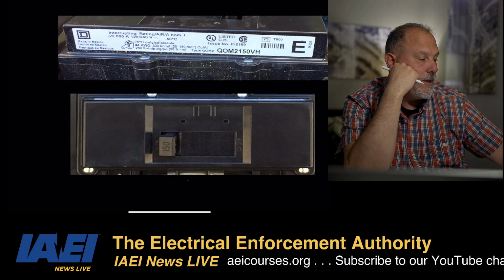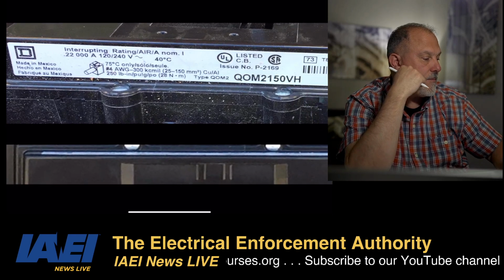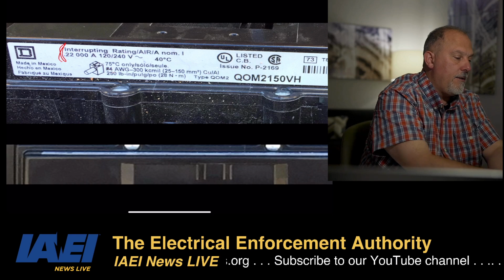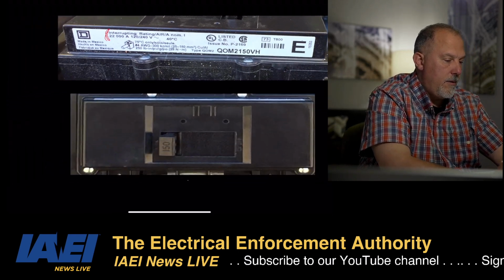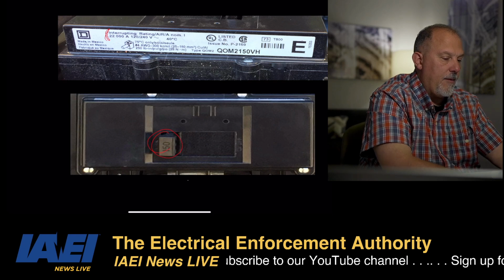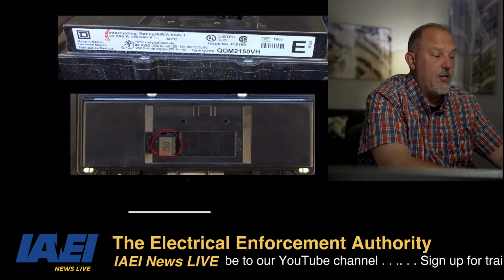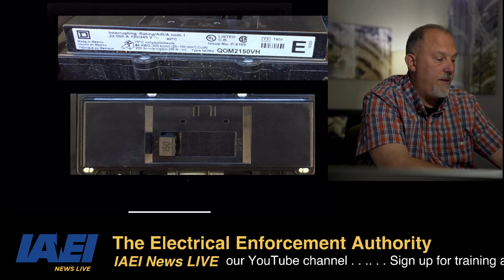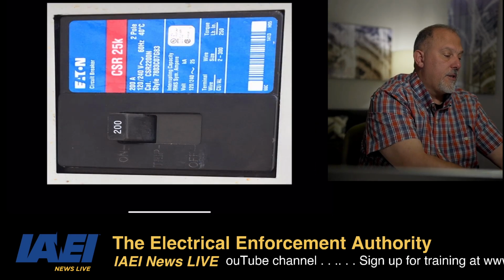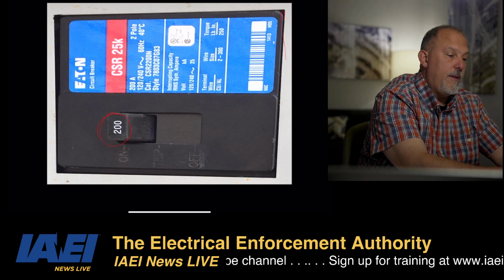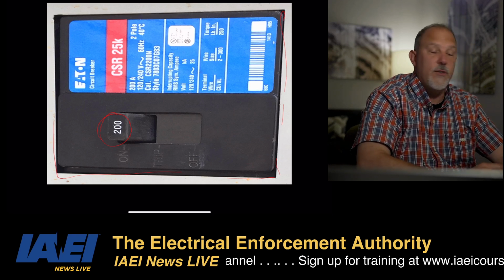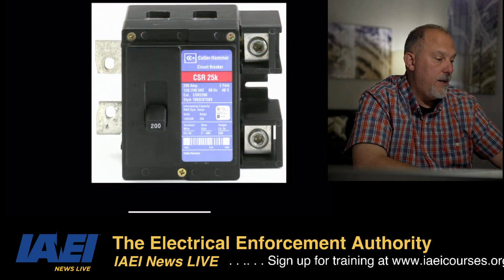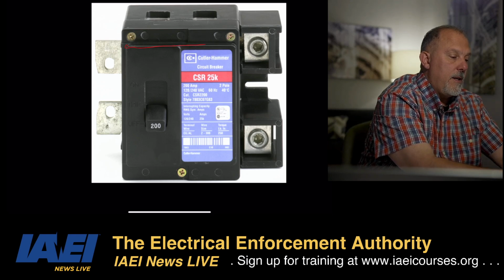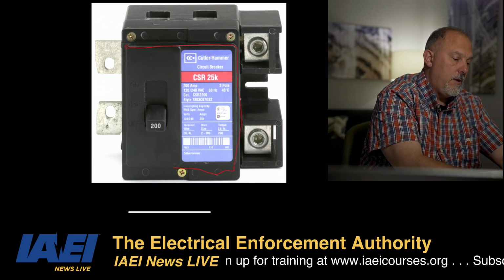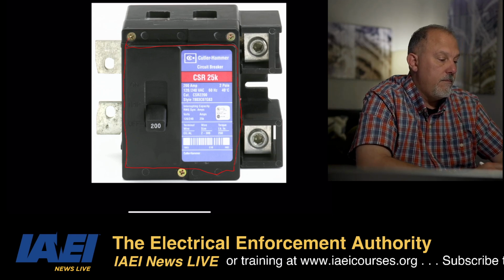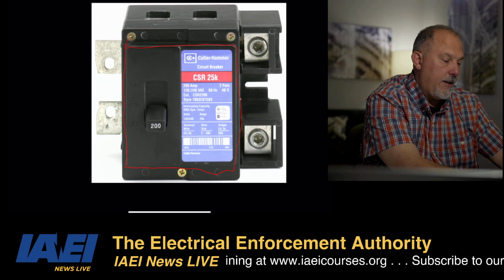Here's a Square D device. There's your interrupting rating right here. And this is a 150 amp breaker, so this is at any convenient location that would not be visible through the dead front. This is a 200 amp device, and this is the dead front, so this is all visible through the dead front. This is visible through the dead front, right? And the interrupting rating is where?